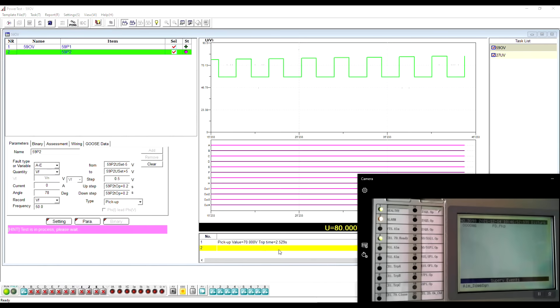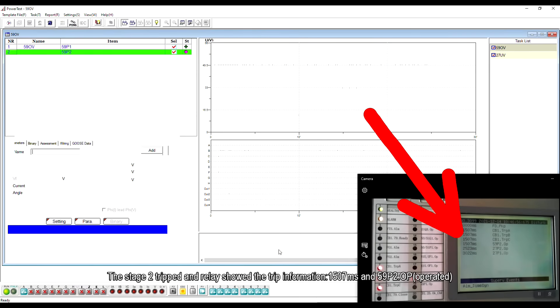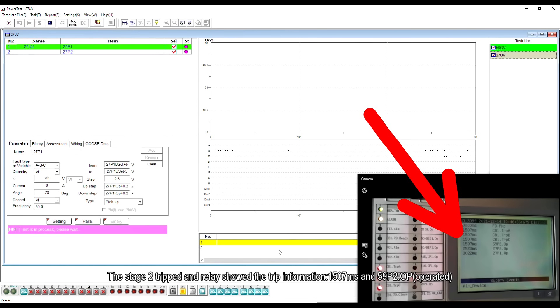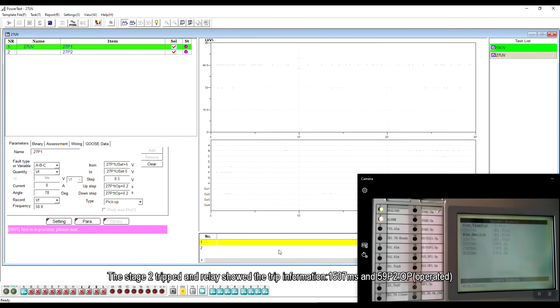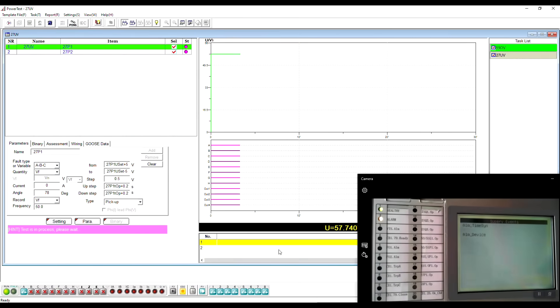The stage 2 tripped and the relay showed the trip information, 1507 ms and 59P2 operated.